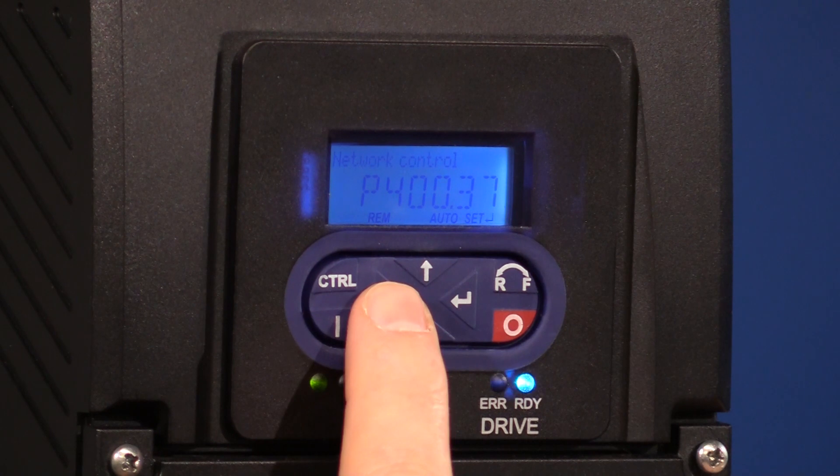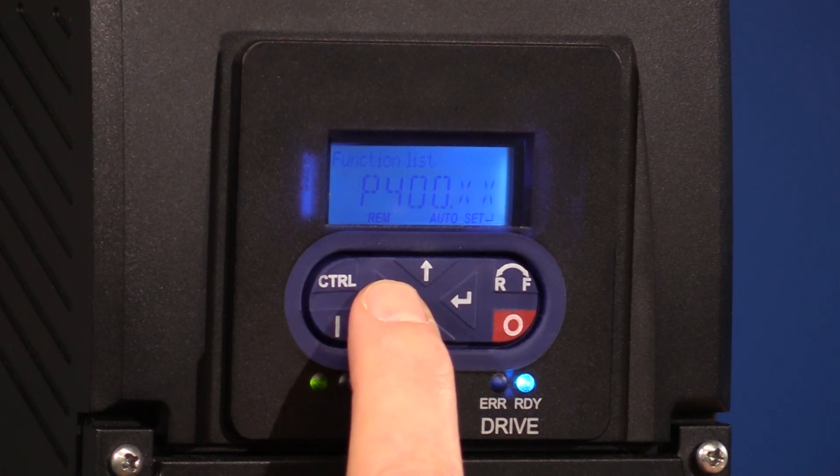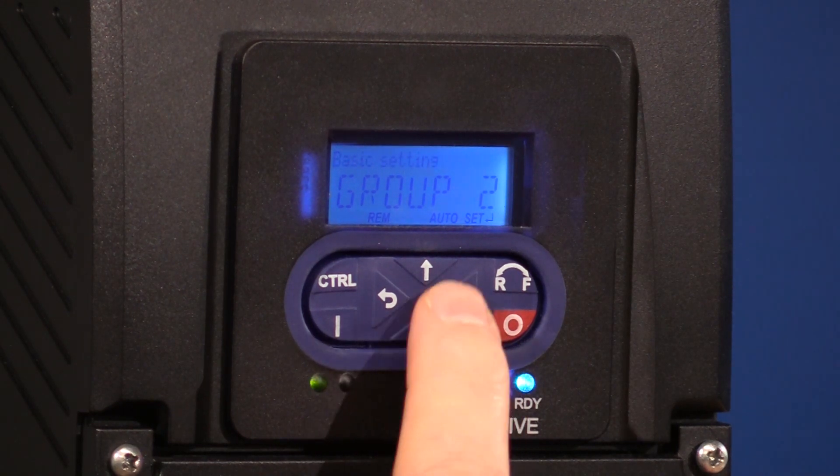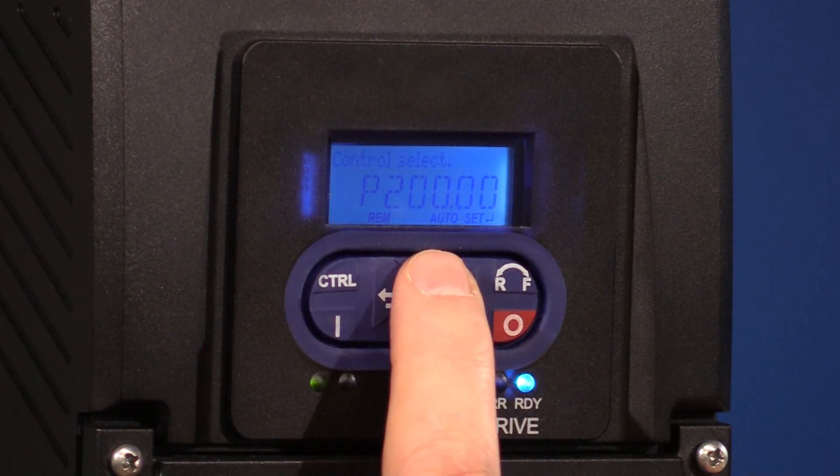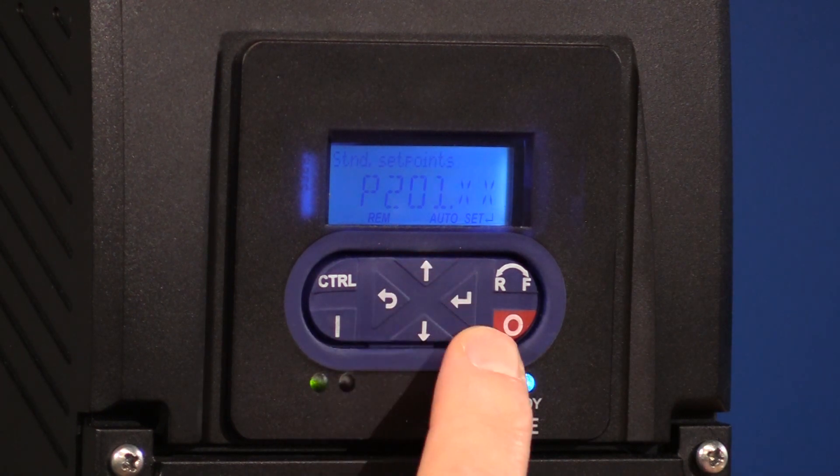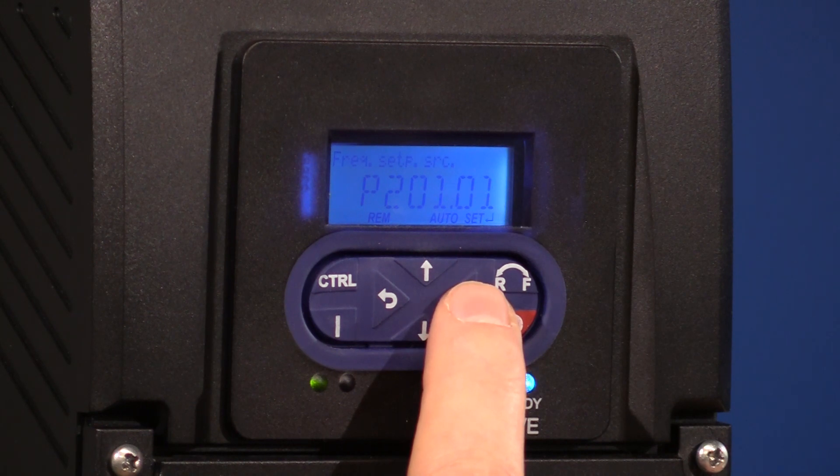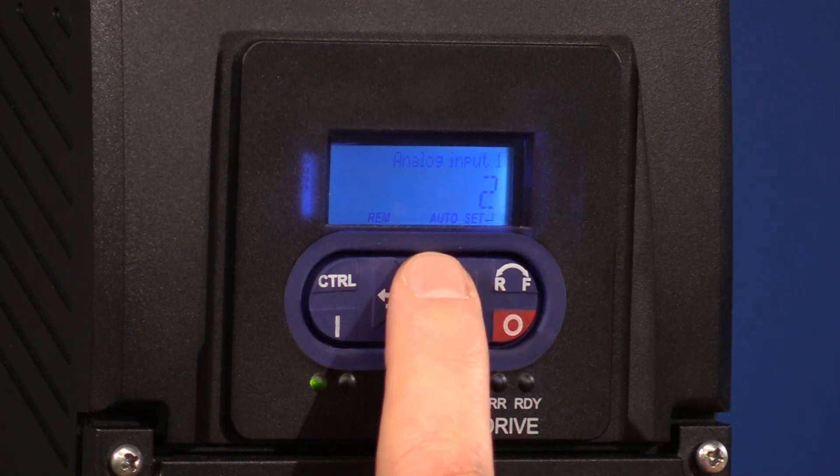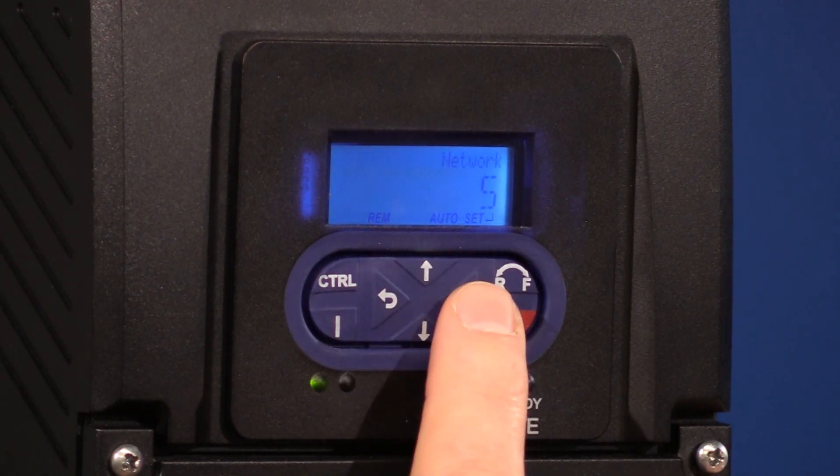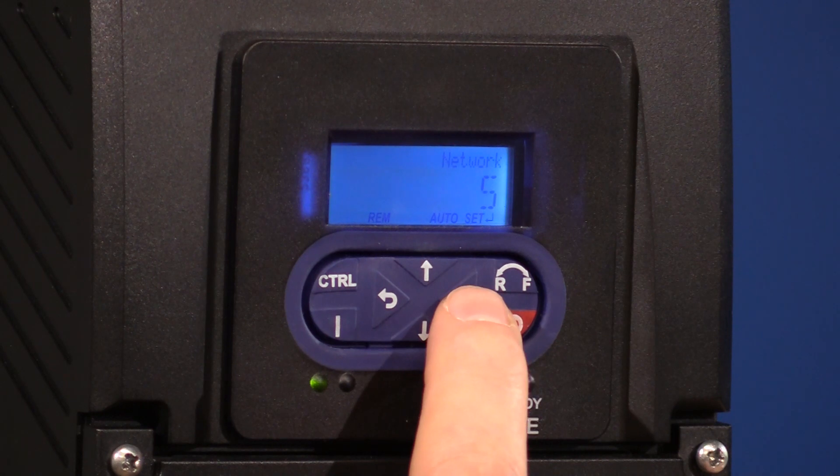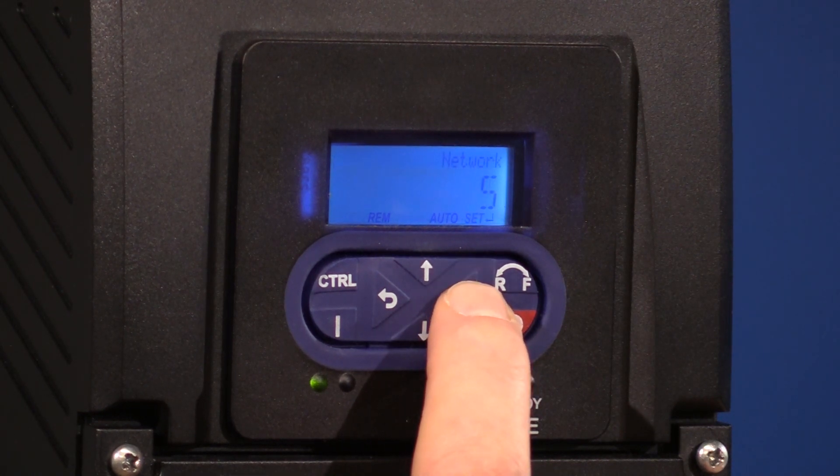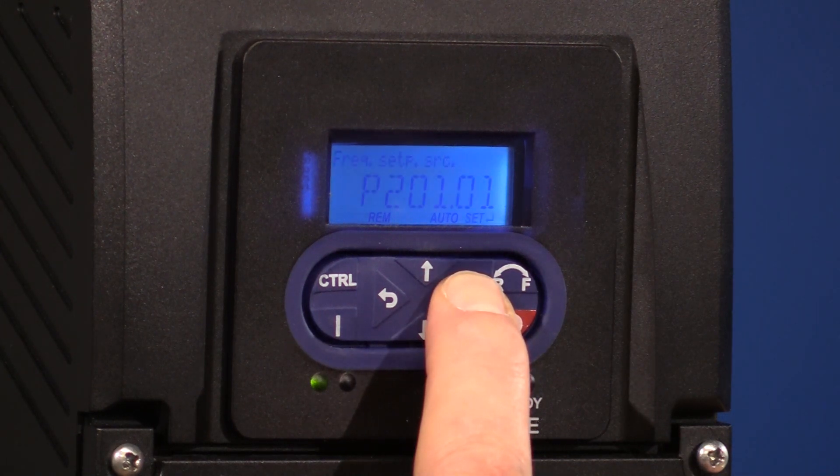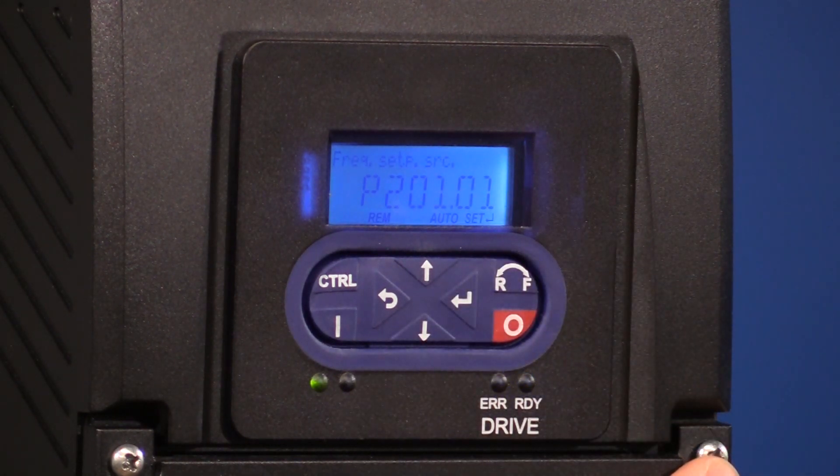The next parameter we want is in 201. So we're going to go back to group two. Use the down arrows. And once you're at group two, press enter. And now we're going to go up to group 201. And we're going to press enter again. And once we're in 201, frequency control, we're going to press enter. And we're going to set it to five, which is network. We're going to press enter again. And now we're going to hold the enter button. Once we set it to five, we're going to hold the enter button down. And now the parameter is saved.